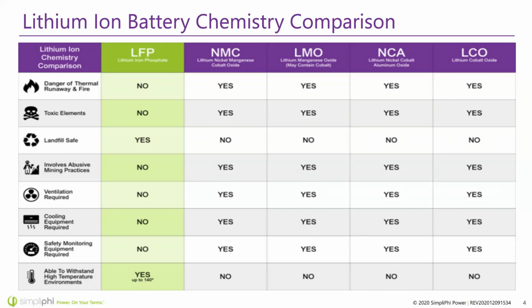So in the category of thermal runaway and fire, is there a risk? Of course there can be. Anything made of a material can catch on fire. But in its ability to propagate fire, to spread it outside of its individual cell, LFP is by far the safest and will not propagate that fire externally. Whereas other lithium chemistries, most commonly NMC, LMO, NCA, and LCO, all inherently have cobalt in them, which is the property that propagates fire externally and runs rampant, whether the fire is internal to the battery or external, like from the home or garage. So in terms of safety, LFP is second to none.